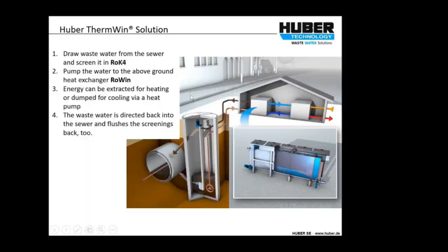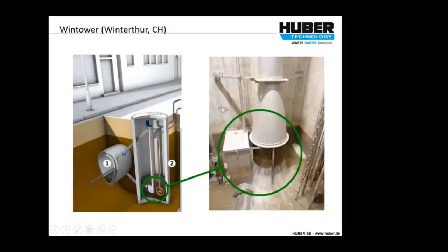So this is an actual installation in a place called Winterthur in Switzerland. You can see here that there's an intervention into the sewer, and it comes into the inside of the screen there, and then the sewage comes out, and this is a lifting chain for a pump that takes the pump out here. So the sewage comes in through that pipe into the screen. The screenings are conveyed up that pipe there, which is this pipe here, and discharged back into the sewer. And this sewage here is available for heating, and it goes up here, and that will discharge somewhere over here back into the sewer as the sewer flows away from the building. So that's the screening element.